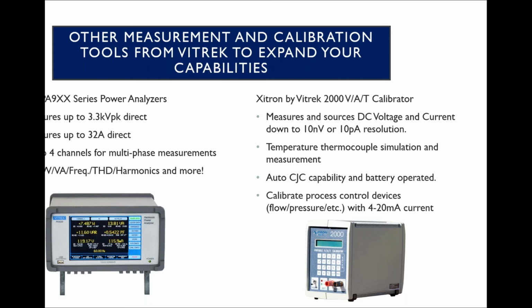So we have the PA9XX series of power analyzers we briefly touched on earlier. These can measure up to 3.3 kV peak direct, as well as 32 amps direct. They have up to 4 channels of power analysis, so that you can achieve 3-phase measurements or efficiency measurements. It includes a wide variety of graphical functions, as well as a scope mode. It has a lot of different measurement categories that it covers, including volts, amps, watts, VA, THD, up to 500 harmonics, along with many more, rectified line, everything.